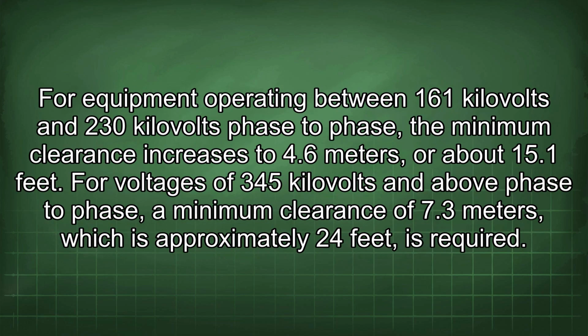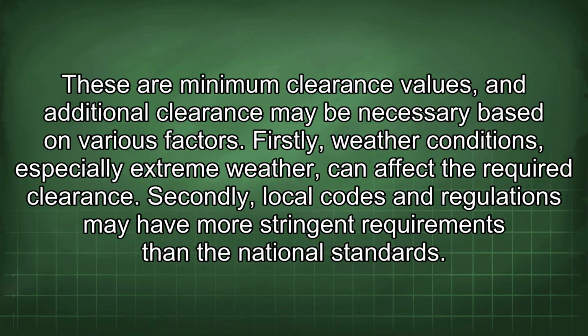For equipment operating between 161 kilovolts and 230 kilovolts phase-to-phase, the minimum clearance increases to 4.6 meters, or about 15.1 feet. For voltages of 345 kilovolts and above phase-to-phase, a minimum clearance of 7.3 meters, which is approximately 24 feet, is required. These are minimum clearance values, and additional clearance may be necessary based on various factors.